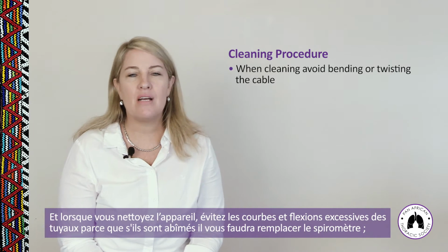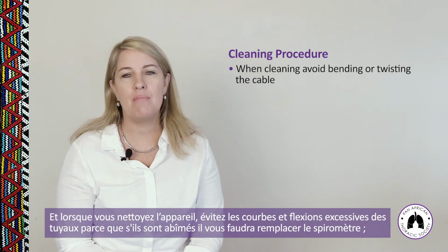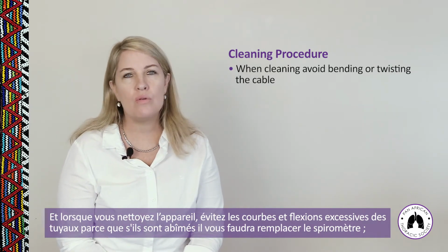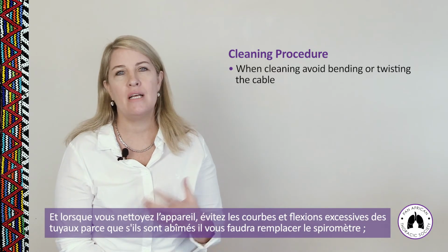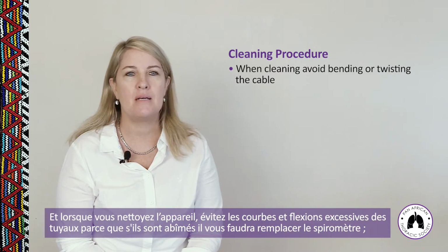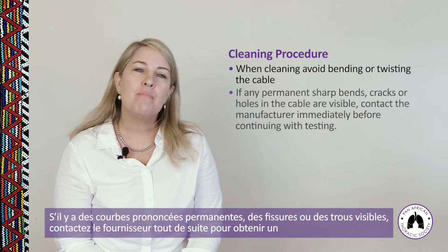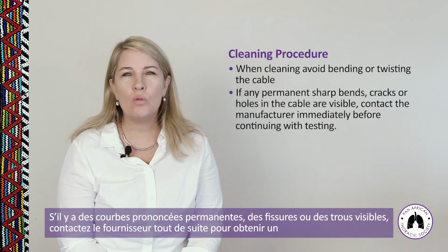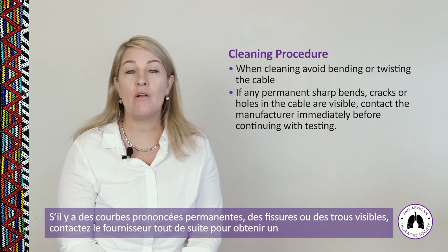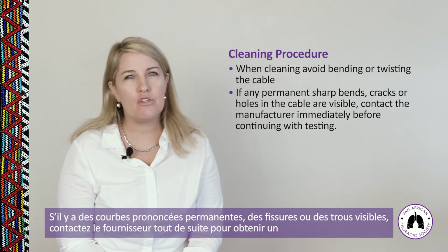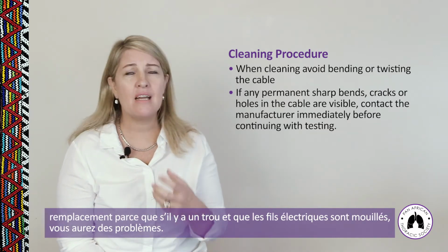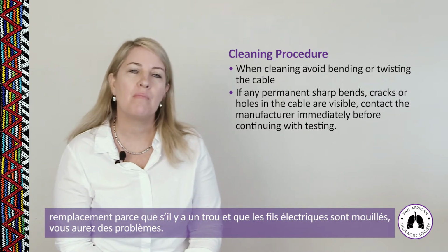When cleaning the device, avoid bending or twisting the cables because that can cause damage to the cables eventually and ultimately the demise of your spirometer. If there are any permanent sharp cracks, bends, or holes in the spirometry cables that are visible, contact the manufacturer to replace that, because if you clean that and it gets into the electrics, you could have a problem there.